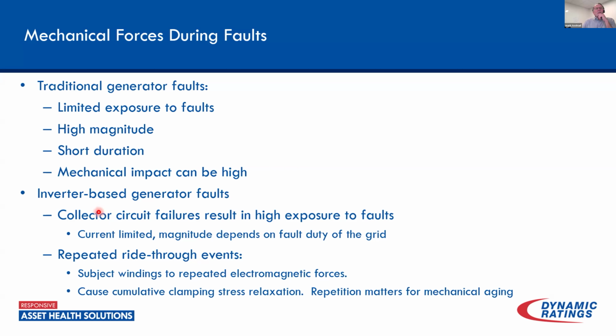With inverter-based generation, the fault currents tend to be lower. The inverter outputs are current limited, so we're not as worried about the levels of the faults. It could be high if it's in an area of the grid that has a high fault duty, but the generation itself isn't going to supply a lot of fault current because of the current limiting capacity of the inverters. What can happen, though, is there can be a significant increase in the number of faults that the transformer, or the GSU, is going to see. And as we increase it, there could still be a cumulative effect of those faults on the transformer itself.